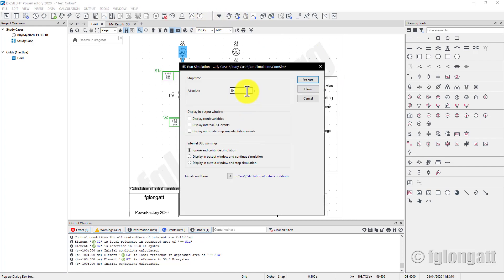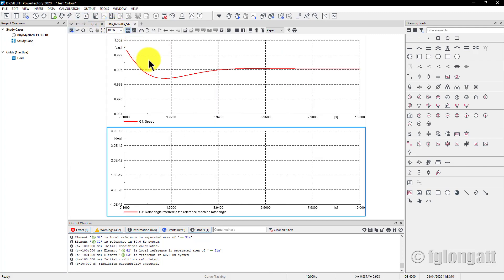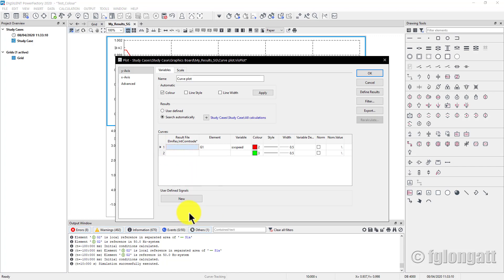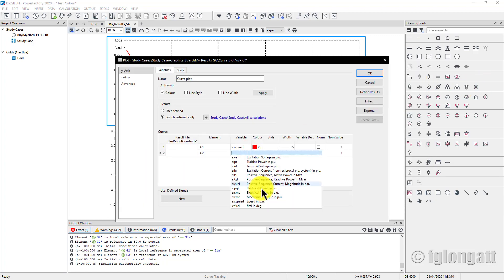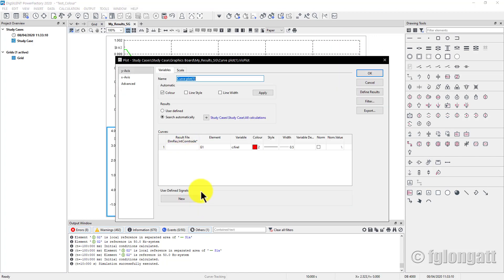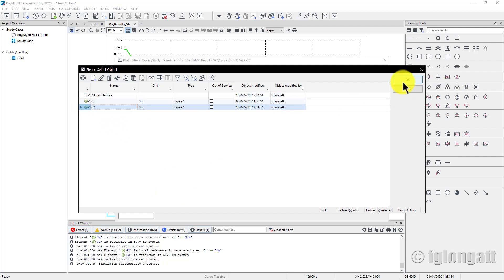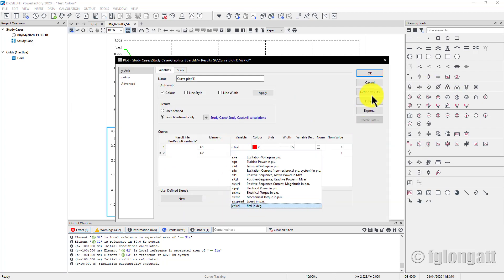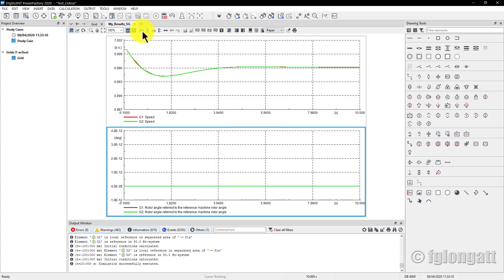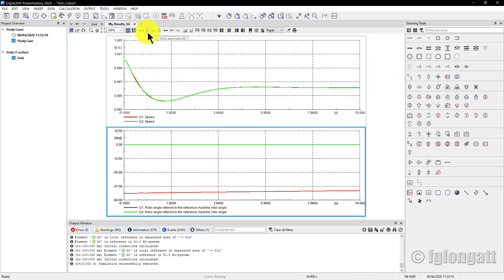I run the initial conditions and a 10-second simulation. In the plot I append a row for the rotor speed of Generator 2 and another row for the rotor angle of Generator 2. As you can see, there are two results: rotor speed for Generator 1, rotor speed for Generator 2, and the same for the rotor angle — confirming both generators with their controllers are working correctly.